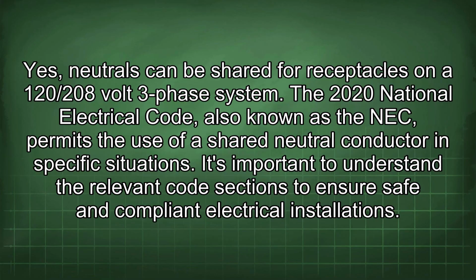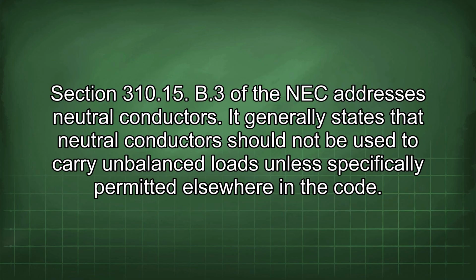Yes, neutrals can be shared for receptacles on a 120/208 volt three-phase system. The 2020 National Electrical Code, also known as the NEC, permits the use of a shared neutral conductor in specific situations. It's important to understand the relevant code sections to ensure safe and compliant electrical installations. Section 310.15 B3 of the NEC addresses neutral conductors.